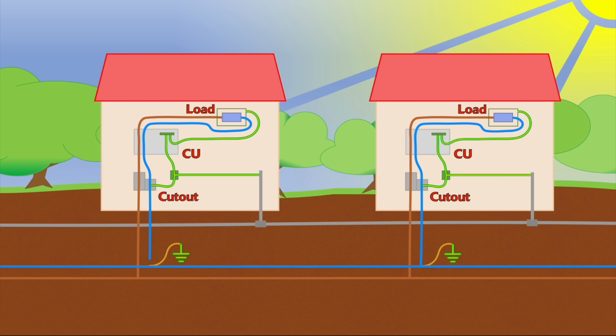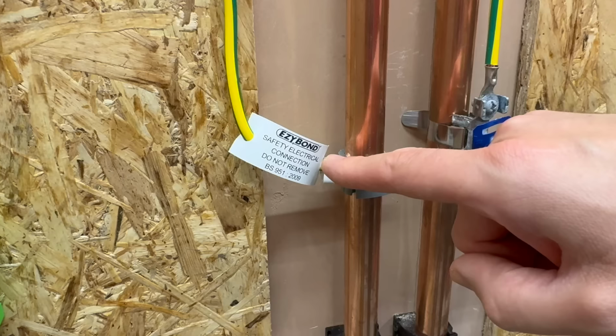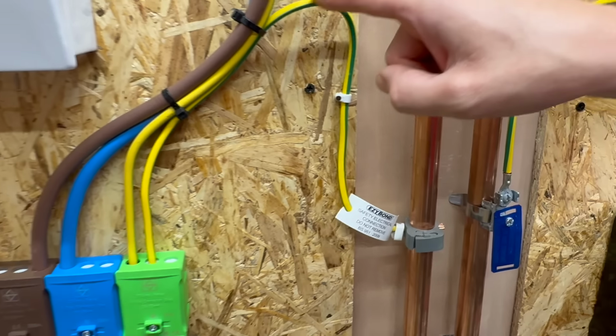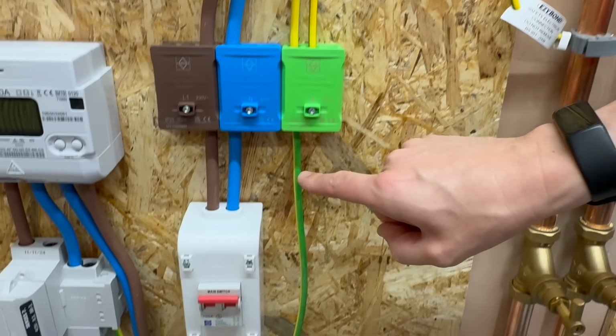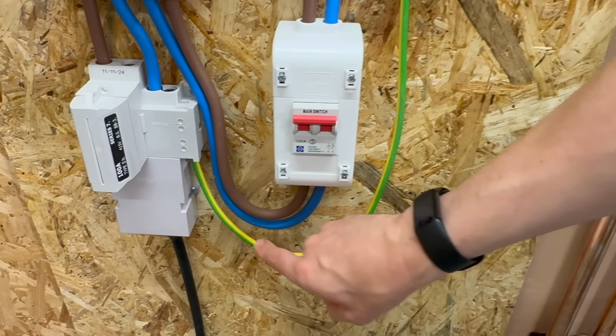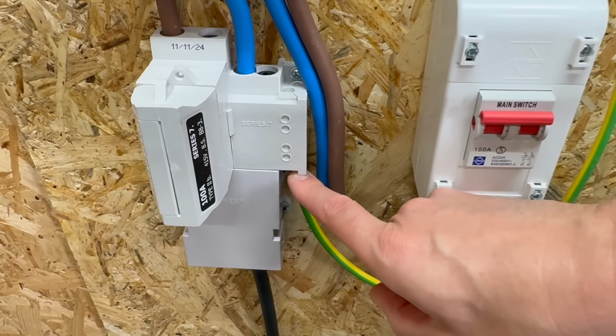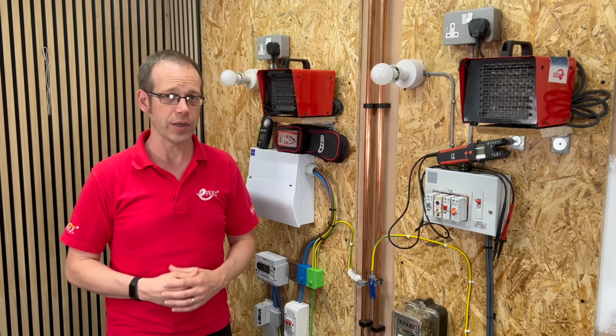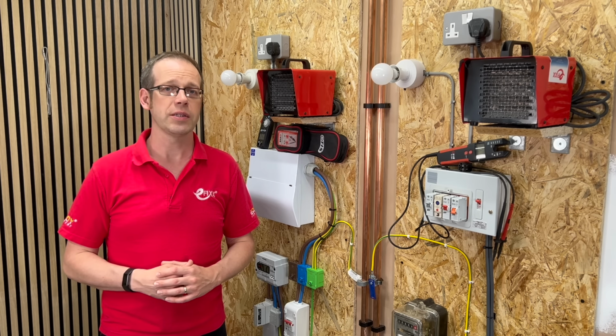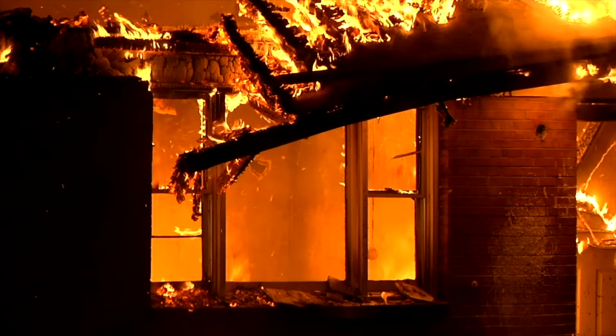If there's a number of houses along this stretch and further faults occur in a certain way, then these conductors may end up carrying the full load current of several properties. That means this conductor may start to carry more current than it was ever designed for, and there's no protective device to halt that situation. While it may not necessarily cause a shock risk, that amount of current can generate some serious heat and could start a fire.